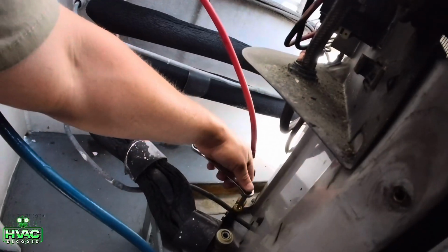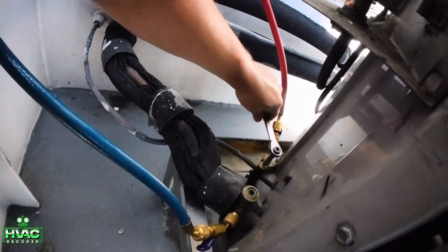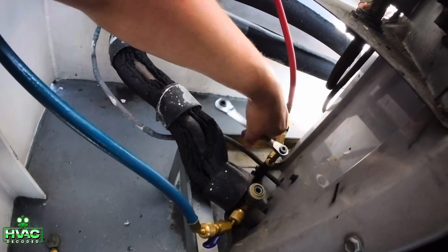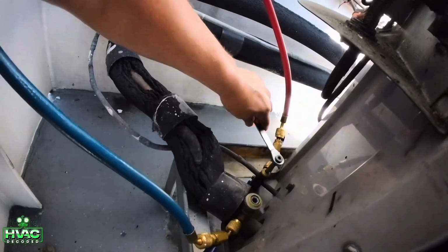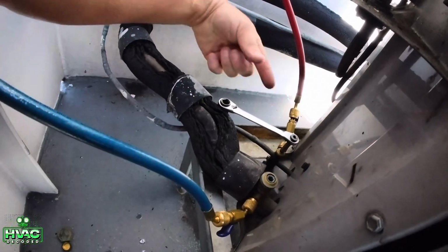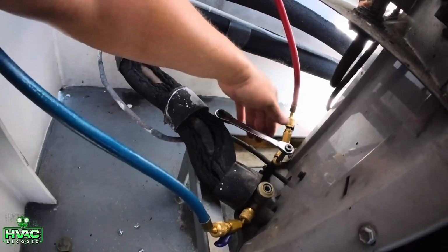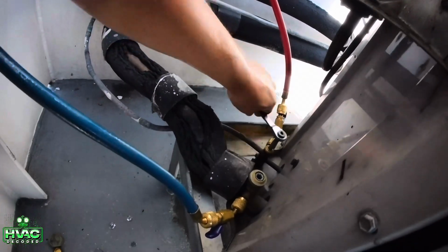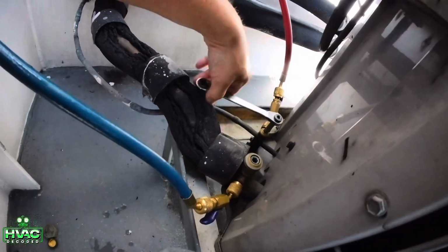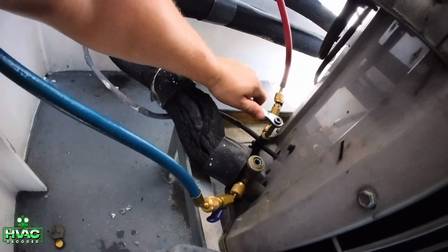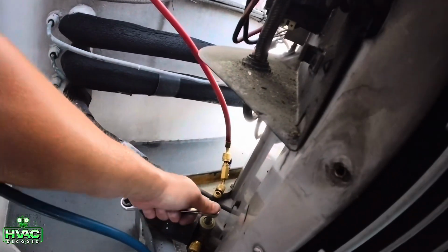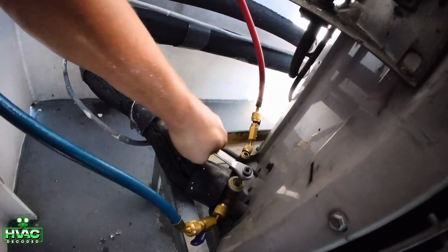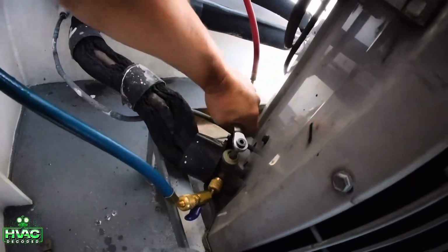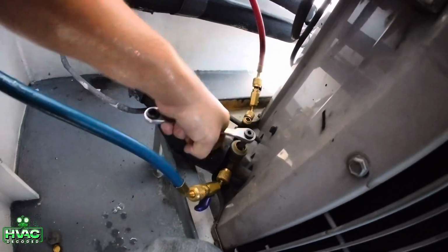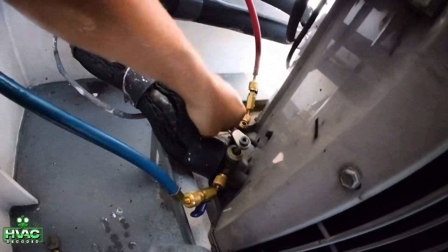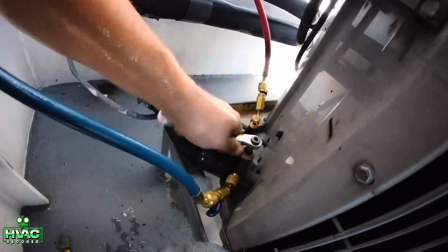Close down the liquid side, right? Because the compressor is going to pump, pull it, suck it into the compressor, into the condenser, and it'll stop here on my liquid line. That's how it's pumped down, all into the condenser. What I like to do with the suction is get it all the way down and then back it out, because they're so long-winded, so that whenever I'm ready to close it, I've only got a few turns to do, not all these.